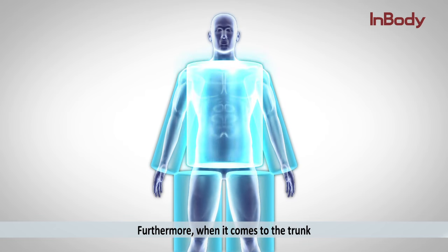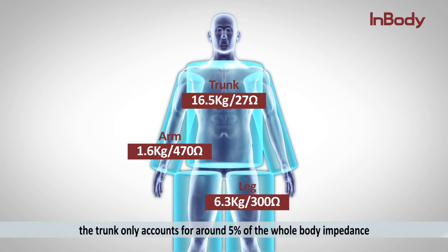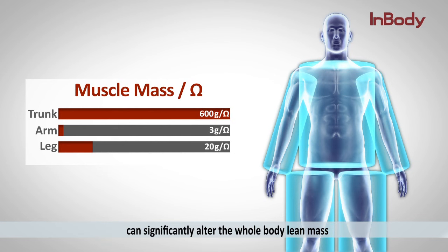Furthermore, when it comes to the trunk, its short and wide cylindrical shape yields a very low impedance value. The trunk only accounts for around five percent of the whole body impedance, yet it is responsible for about 50 percent of the whole body mass. This indicates that even a small change of one to two ohms in the trunk impedance value can significantly alter the whole body lean mass measurement.